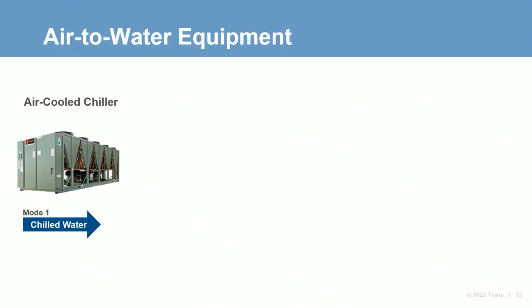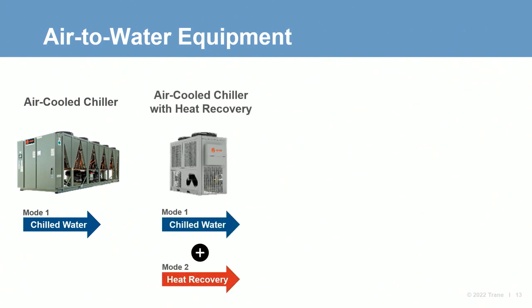The first and the most well-known is just an air-cooled chiller. We use the ambient air as a sink to reject BTUs from the chilled water stream to create that chilled water. The second iteration on this would be to add a secondary heat exchanger to the air-cooled chiller. This would allow the unit to divert hot gas away from the condenser coil and to that secondary heat exchanger. The heat exchanger would be hooked up to a hot water system and allow the building to capture that rejected heat for simultaneous cooling and heating loads. This type of product would not incorporate a reversing valve and would only be able to provide useful heat when a cooling load is present.